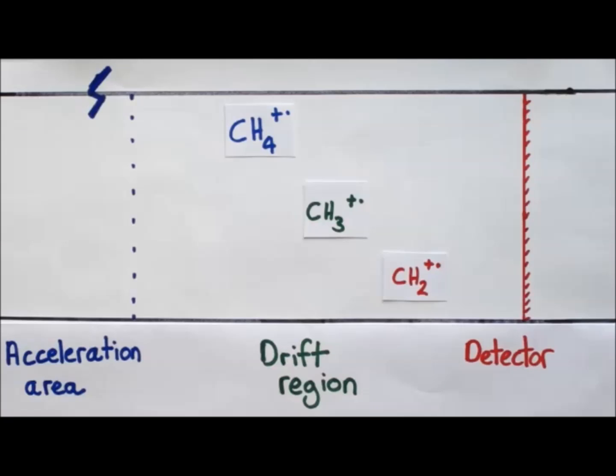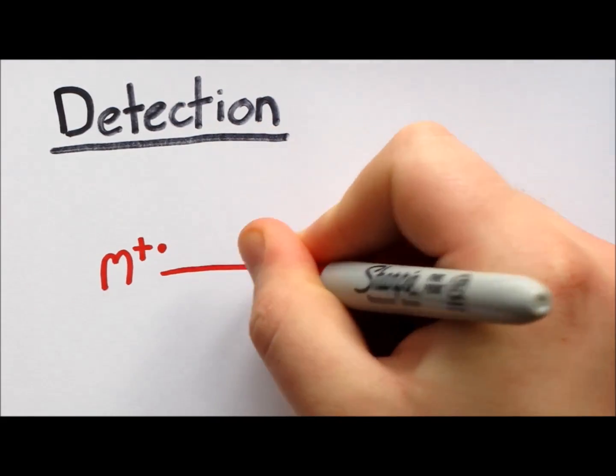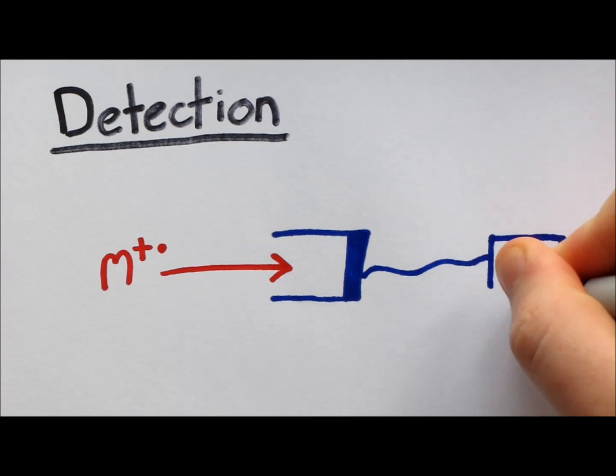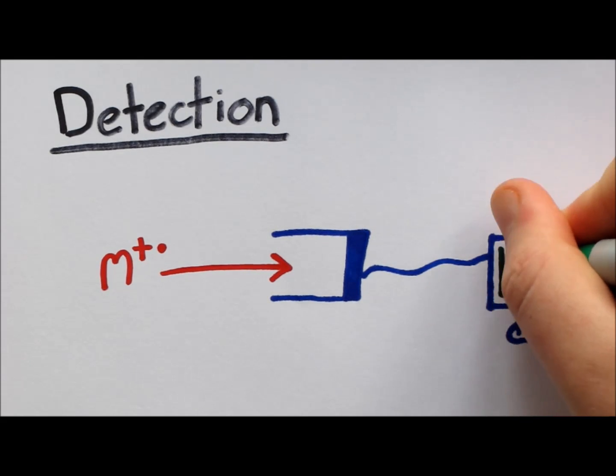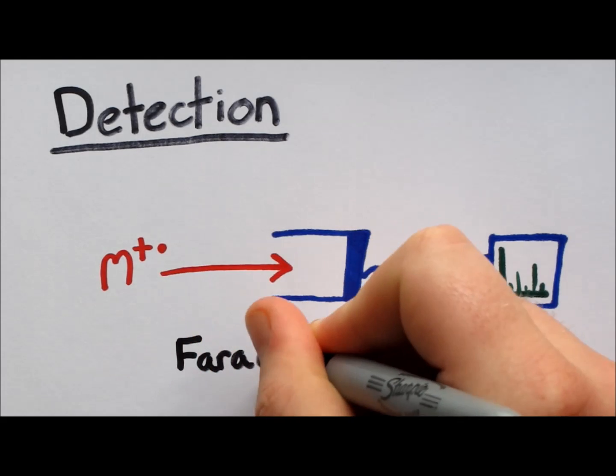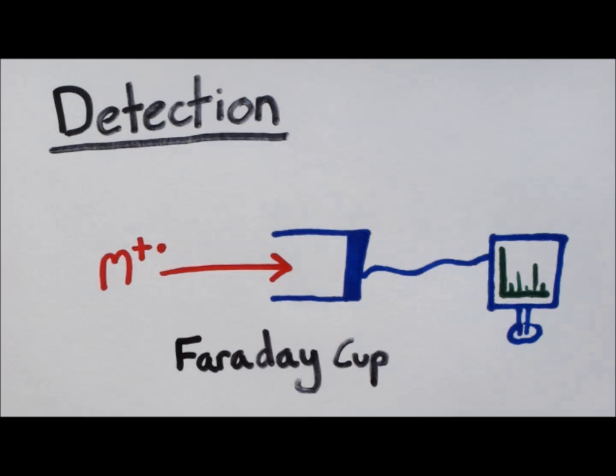At the end of the drift region is the detector. The detector is simply a metal plate that when hit by an ion gets a small charge induced. This is then discharged to give a current proportional to the number of ions hitting the detector. This allows the data to be supplied to a computer. This type of detector is known as a Faraday cup.